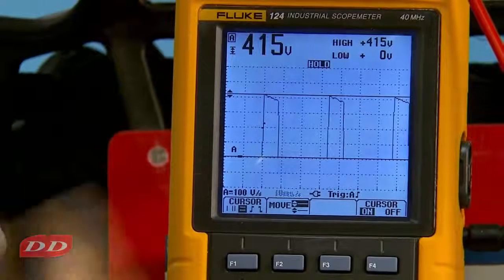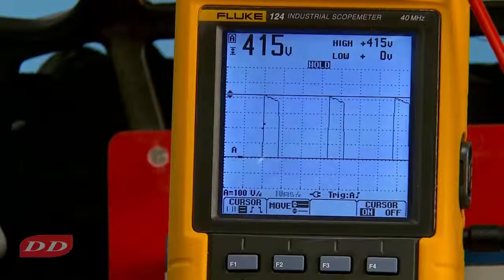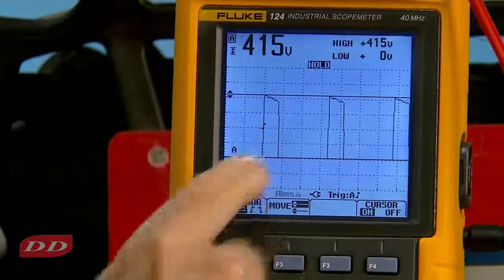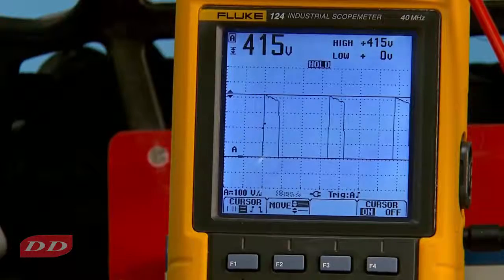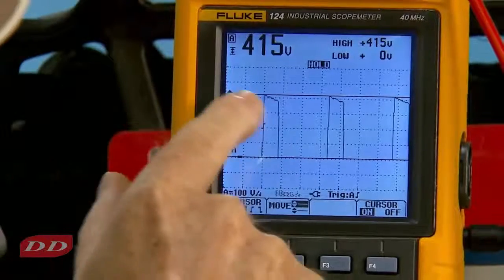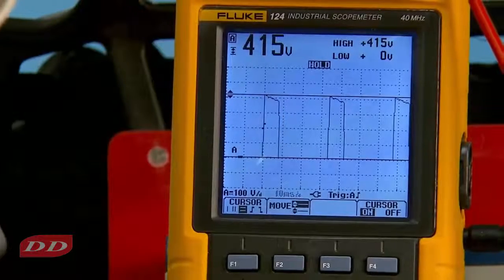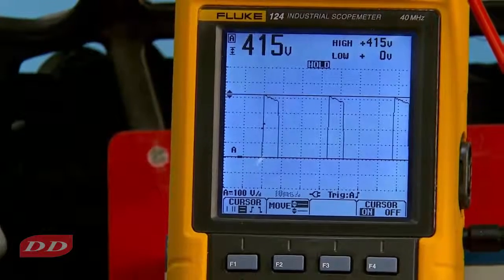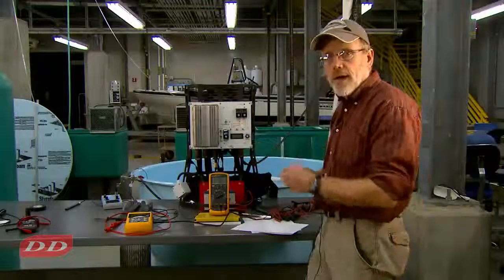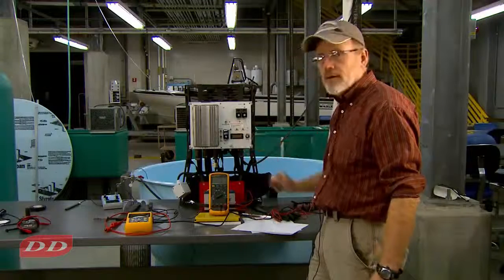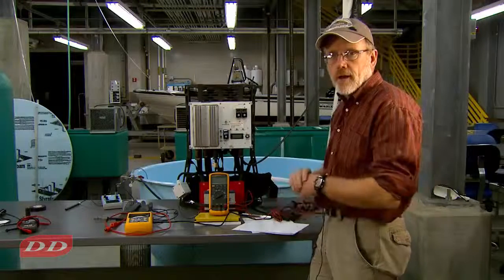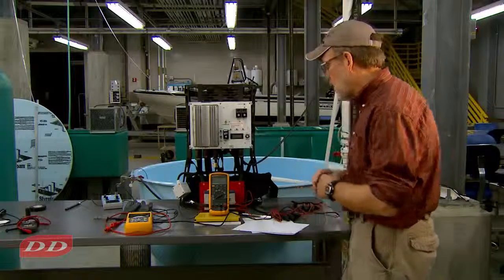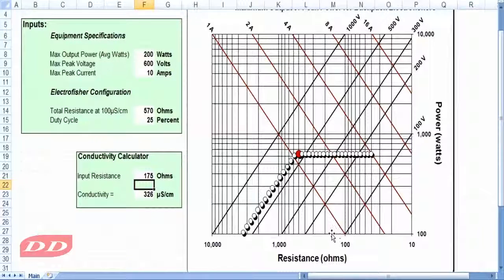So this is again why you want a scope meter if possible, because at high loading the square waves do tend to deteriorate, where they get a spike or a slanted top, and that's what we're seeing here in this instance, and the reason for the discrepancies.